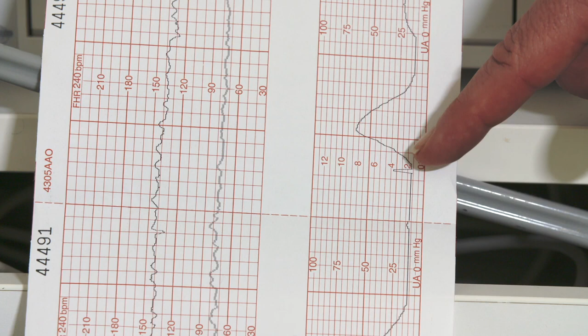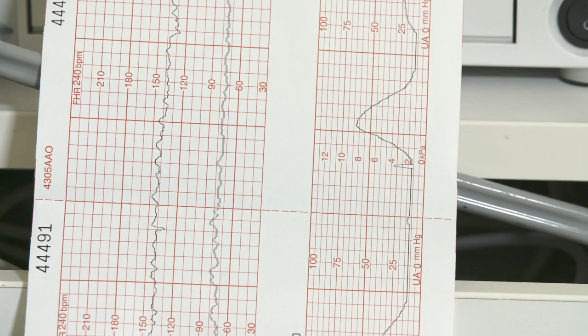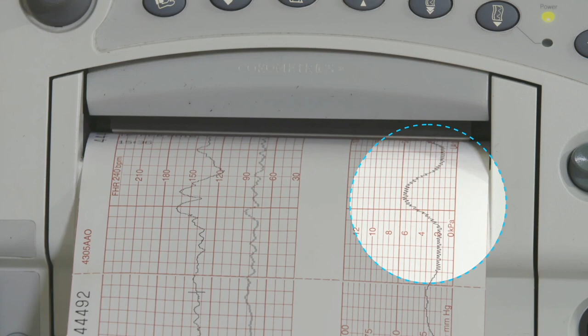To help identify a Novii monitoring session during monitoring, every 5 minutes a spike will appear on the UA trace. The final trace identifier used by Novii is to show when the mom is ambulating. This is done by thickening the UA trace whenever there has been continuous patient movement for 20 seconds or more. This provides context for any trace interpretation.